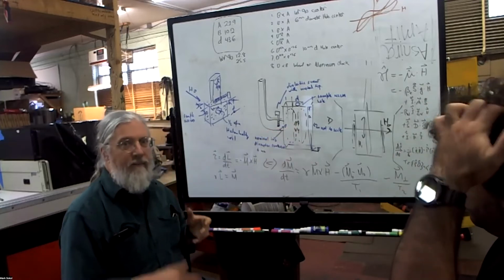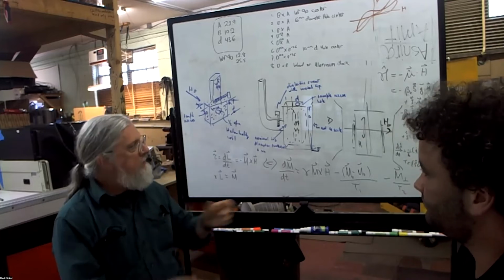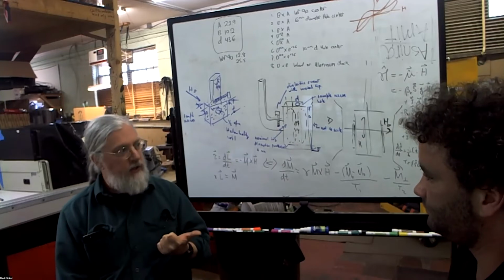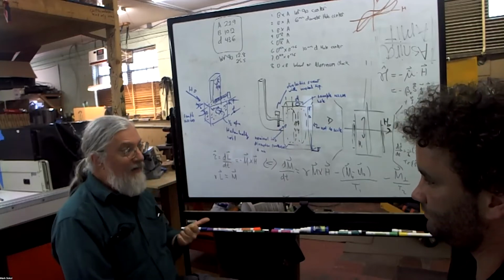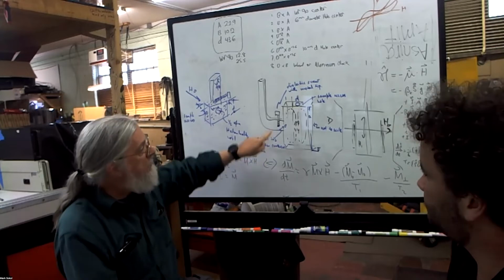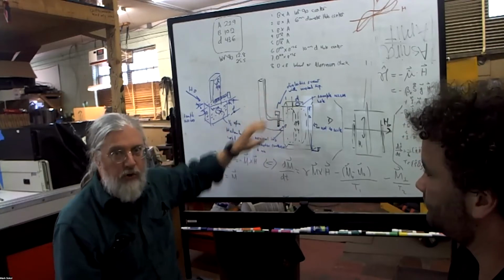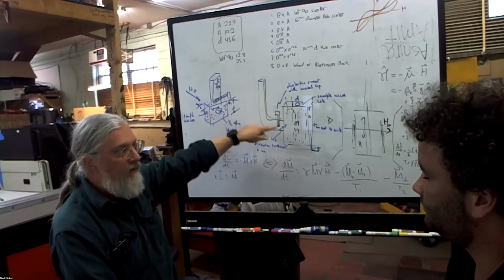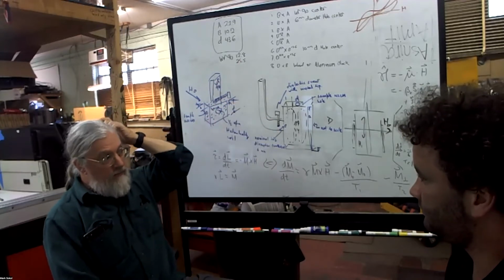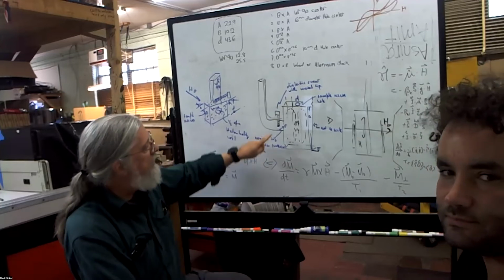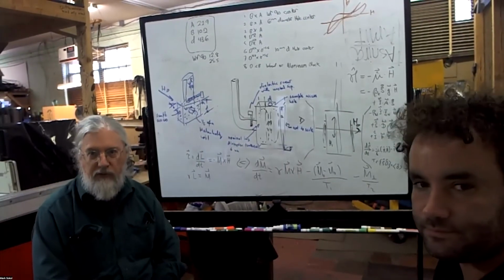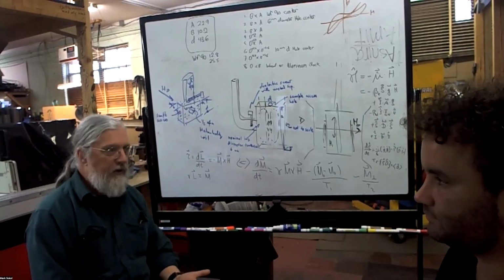And if EPR resonance occurs, that means that there's absorption in the sample. But when there's absorption in the sample, that means that there's additional absorption in the cavity that you haven't accounted for, which means that the position of this tuning screw is wrong in some sense, and you'll start to see a reflected wave from the cavity. And it's impedance matching. Exactly. This is precisely like an impedance matching transformer. And so it's this reflected wave that is what is observed in a classic magnetic resonance experiment.